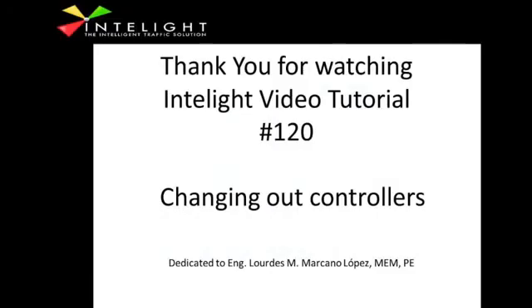Just to recap, the 4 basic steps are: save the database, copy the database out, usually to USB, but you can do it to your computer if you will. Copy it into the other controller and select it. Reboot, and you're pretty much done, and that's it. Thank you for watching this tutorial with me. It's a pretty simple operation, but it's always nice to have a list of the steps and procedures when you're doing the operation.